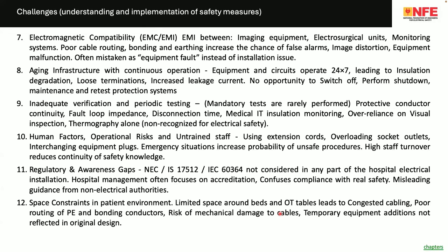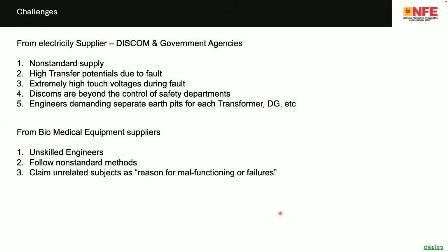And the challenges because of these issues, I put as understanding and implementation of the safety measures in the location. There are challenges with respect to the electricity supplier, that means the distribution company, and the government agencies, those who are supposed to ensure safety. From the DISCOM point of view, non-standard supply. Of course, there are regulations which say how the distribution company should give electricity to a consumer premise, and in the majority of the cases, if this is violated, of course, the consumer is in trouble. High transfer potential due to fault. Whenever there is a fault on the high voltage side of the distribution company, the transfer potentials are killing the equipment.